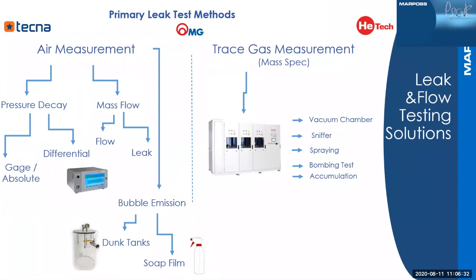Next, we take an overall look at the primary leak test methods that Marposs uses. First, the air measurement side: pressure decay with gauge and absolute test method, and differential pressure decay test method. We have mass flow with two methods, flow and leak. We also have a third method, bubble emission, dunk tanks and soap film. Then there are the trace gas measurement systems: vacuum chambers, sniffer, spraying, bombing test, and accumulation.